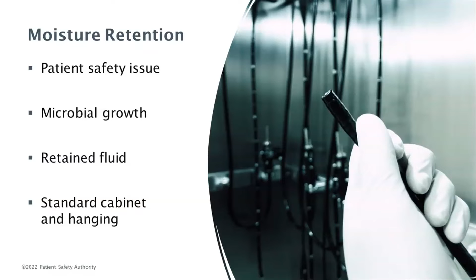There are medical grade forced air pressure devices that allow you to reach that threshold that's recommended for drying. So again, assessing the dryness of a large diameter channel can be accomplished by paper indicators or borescopes. So this is something to consider. Standard cabinet and hanging. And so there are newer devices out there where you have HEPA filtered ultraviolet light type devices, cabinets that are available to hang your endoscopes in. And as we go through this presentation, we'll share more information about those cabinets.